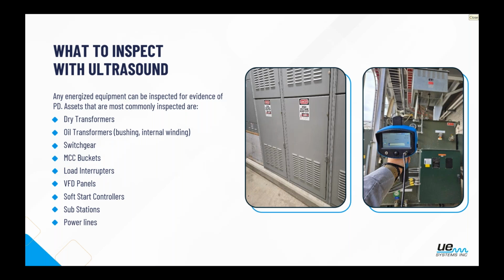We can inspect oil transformers. Specifically, what we'd be listening to is the bushing on top. So as in the image on the right, just make an inspection where the connection is on top, because we could hear something mechanically loose up there, or possibly damage to those ceramics rattling. We do have the ability to listen to the internal winding, but that is something that we don't typically recommend because that changes it from non-contact to a contact method. But just something to be aware of.